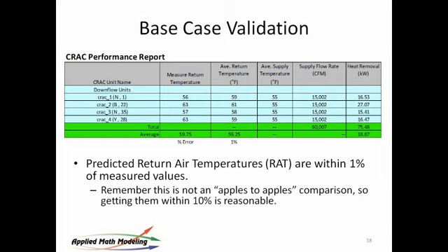In CFD, we have a mesh. A mesh is a polygonal representation that sits on top of that CRAC unit, and the mesh is fine enough so that we have many points on that surface. So ours is actually an average of all of the points on the surface, instead of just one point. So it really isn't fair, even Liz here, to say average return. No, I did say measured. I called it measured return, but this is a point, and this is really an average. They're really not apples to apples. Right. So 10% is reasonable, is my point here. If you're within 10%, you've captured the dominant physics in the room.